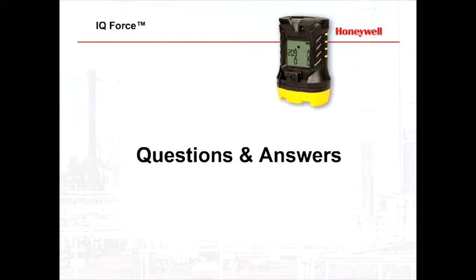Does an operator need to use a dock to program or calibrate the IQ Force? No. The instrument can be programmed through the use of an IR dongle. So that's something you could connect directly to your PC and configure it through your PC. For calibration, you don't need to use a dock. You can calibrate the detector on its own. It comes with the cal cap in the box, so you could just hook that up directly to a gas tank and calibrate it that way. Again, with the docks, we just think it simplifies your record keeping, and it makes it a lot easier for your guys to calibrate and bump whenever they need to, but you don't need them.